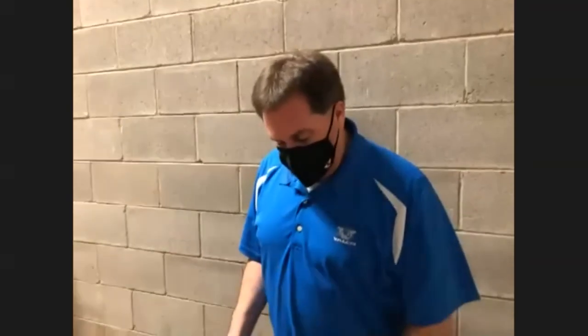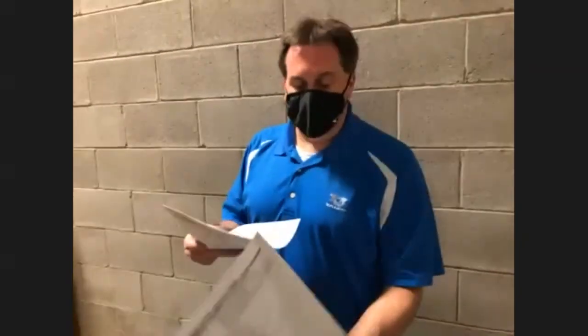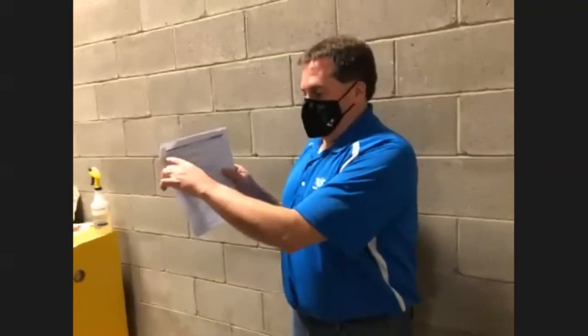More troubleshooting with the gas burners. If you've gone through this general maintenance and what we've just described with the troubleshooting on this gas burner, and you have not found the issue, every gas burner does come with the manufacturer manual as well. In the back of the troubleshooting section of that manual, they have a step-by-step procedure of what to do to make sure everything is checked accordingly. You must follow that step by step. If you only look over some of these steps, you may not find the right correction to your issue.